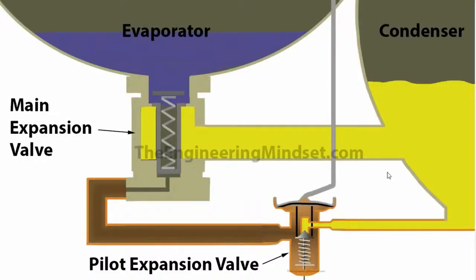So we can look at a section view here. We've got the condenser on the side, the evaporator located above. We've got the capillary tube riding up and connecting onto the suction line. Down the bottom we've got the pilot expansion valve. This is connected through with a liquid line going to the main expansion valve. Inside there is a piston body and spring. This piston body and spring is what will control and allow this refrigerant to flow through into the evaporator.